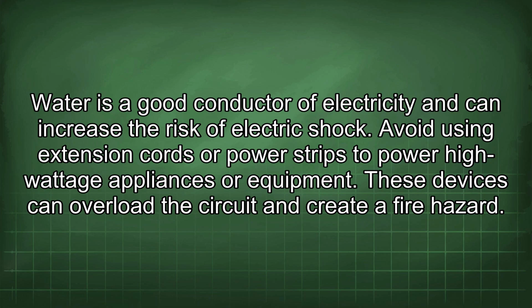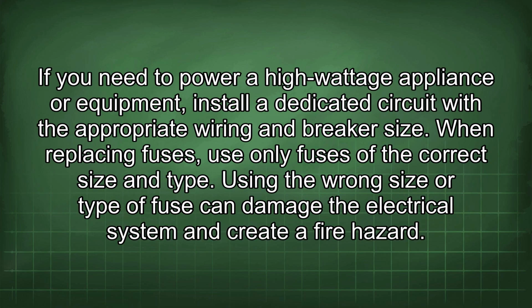Avoid using extension cords or power strips to power high wattage appliances or equipment. These devices can overload the circuit and create a fire hazard. If you need to power a high wattage appliance or equipment, install a dedicated circuit with the appropriate wiring and breaker size. When replacing fuses, use only fuses of the correct size and type.